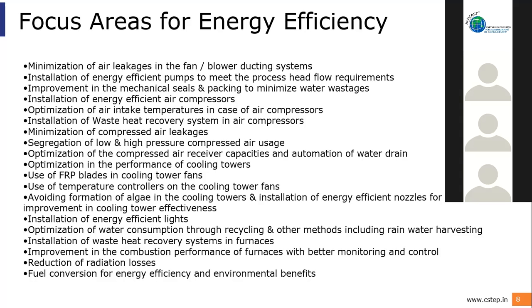And we talk about air compressors. Now, air compressors are another area of focus in the die casting units. Compressor technology has changed over the years, and today we have air compressors with a specific power consumption of around 0.15 kilowatt per CFM. Most of the MSME units I have visited over the past several years work at a specific power consumption of 0.21 kilowatt per CFM at around 7.5 bar. So technology has changed, and the efficiency of air compressors can improve, and compressed air costing is one of the concern areas. Today we even have waste heat recovery from air compressors. These technologies are available. Atlas Copco and other brands are providing waste heat recovery options from the compressors. So this can be utilized.